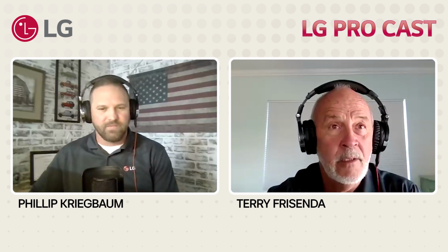Yeah. So the second one that I wanted to hit on, and golly, you just about stole my thunder, is what about, and I was taught the exact same thing, you can't oversize a mini split. Those exact words were said to me. If you look at this data and you look at single zone versus multi zone. And listen, when we're talking single zone, we're talking about one outdoor unit and one indoor unit, the way mini splits were introduced to the United States, right? But when we start talking multi zone and whole home heating and cooling, that's a single outdoor unit connected to multiple indoor units, just like it sounds, right?